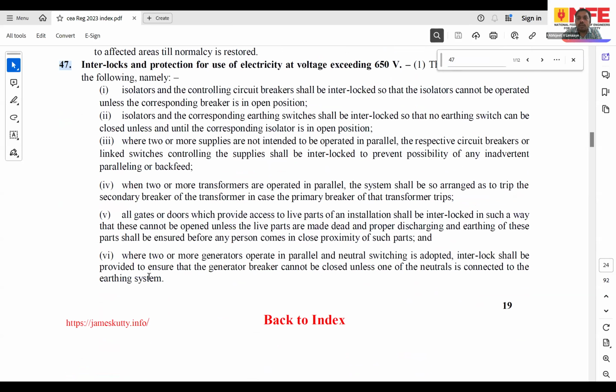However, when it comes to multiple generators and multiple neutral switching, now typically switch neutral is a phenomenon which has only come because of harmonics in the system. So people prefer to have four pole breakers at the generator end in order to ensure that in case of neutral overload, in case of harmonics, these breakers can be tripped.